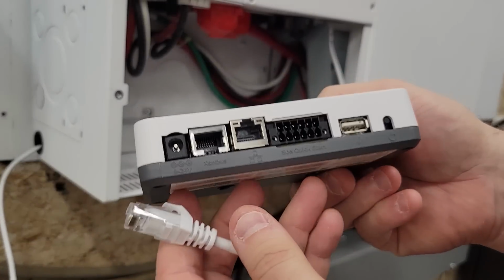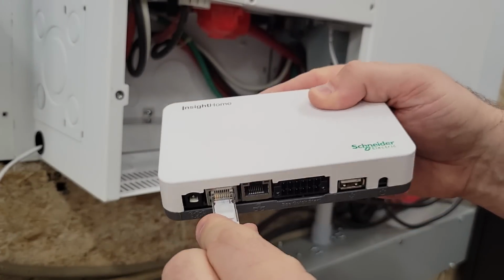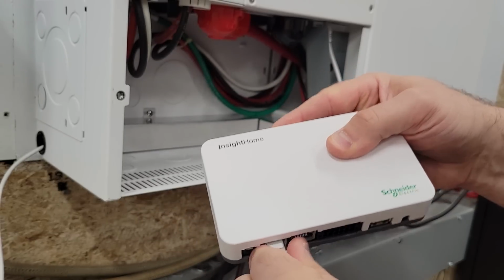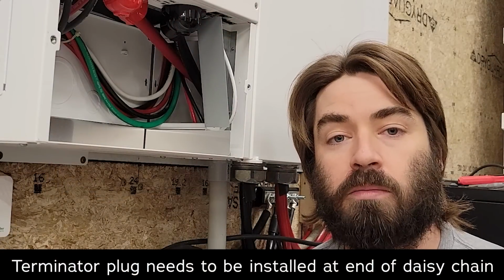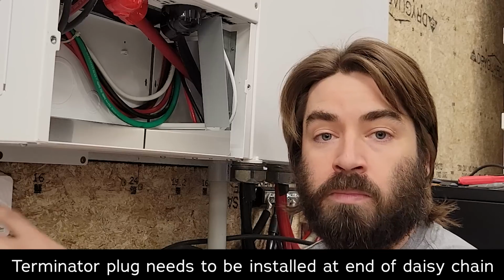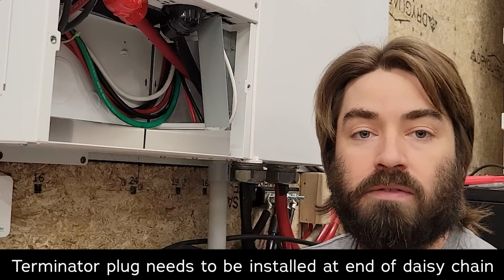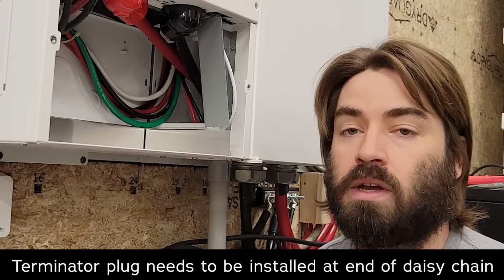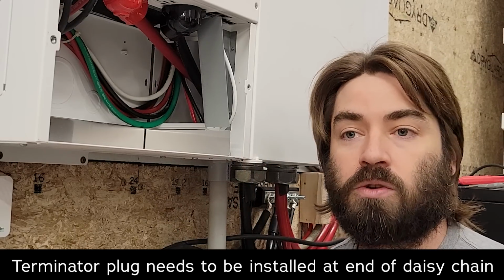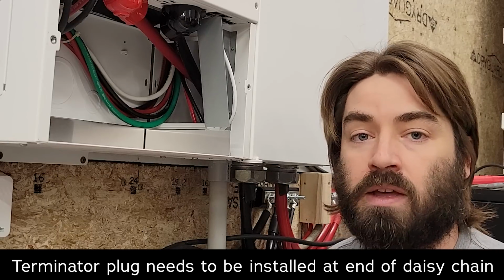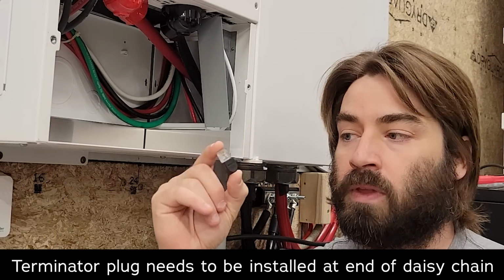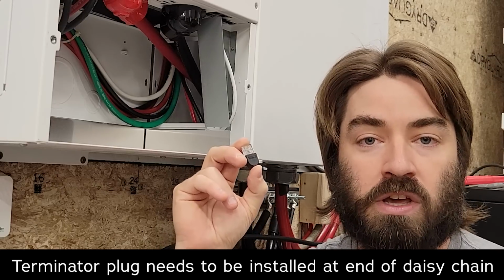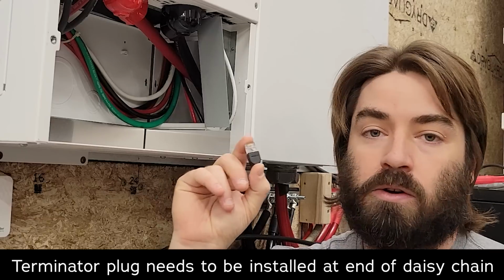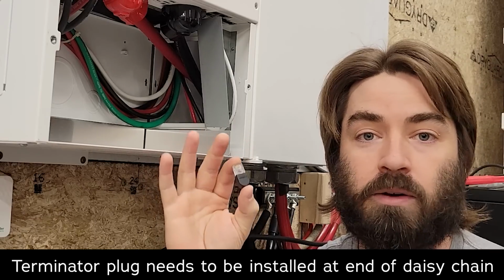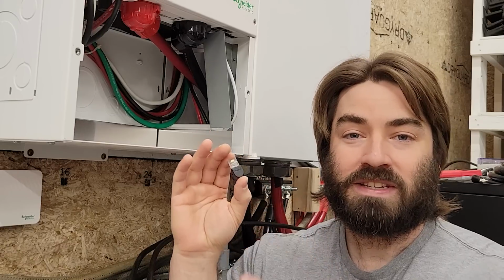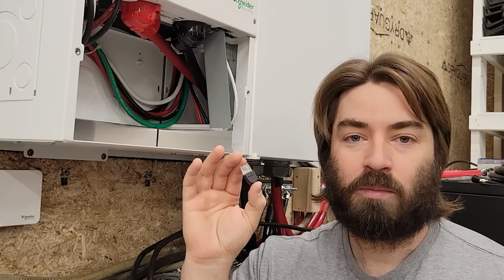All right, on the base of the InsightHome, you can see it says Xanbus right there. So we'll plug it in. Now we're not quite done. We need to terminate the daisy chain. Now the InsightHome is self-terminating, but up here on the inverter, there are two Xanbus ports. One of them needs to be terminated to show that it's not going off to another piece of equipment. The inverter came with a little terminator, and according to one of the webinars that I watched, Schneider does not sell these separately, so if you lose it, I have no idea what you do. So please don't lose this. It comes with the inverter. The InsightHome does not come with a spare.